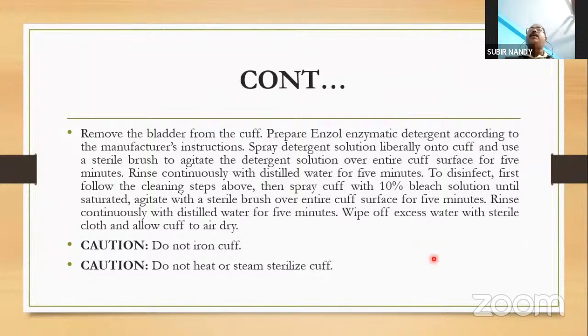Continue. Remove the bladder from the cuff. Prepare enzymatic detergent according to the manufacturer's instructions. Spray detergent solution liberally onto cuff and use a sterile brush to agitate the detergent solution over the entire cuff surface for 5 minutes. Rinse continuously with distilled water for 5 minutes.